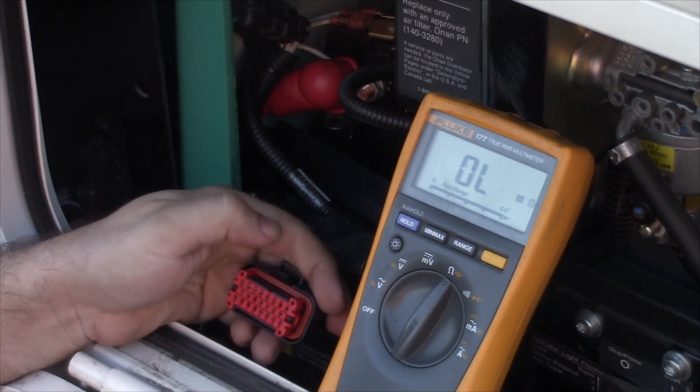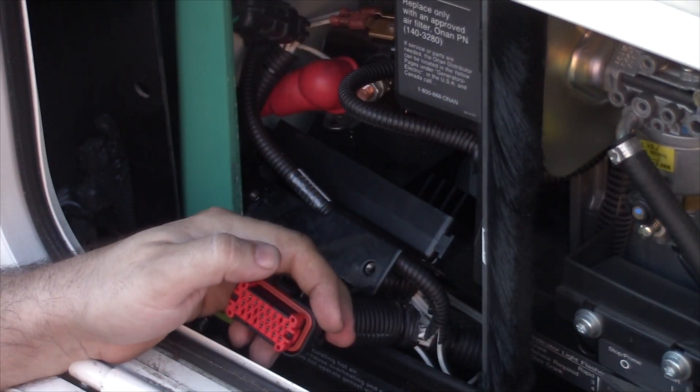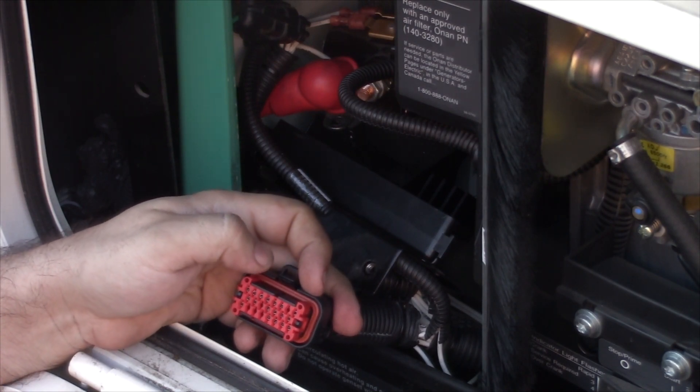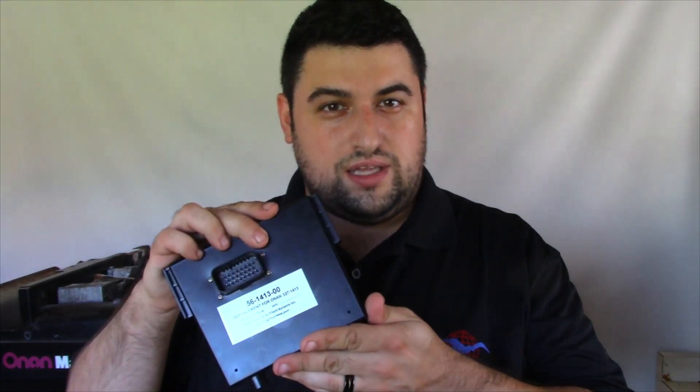That is measuring your windings on the QG4000. The Marquis Gold generators — the early model Marquis Gold generators — use exactly the same connector and it's pinned exactly the same way. That's how you measure the windings on a QG4000 and a Marquis Gold-style generator using that 23-pin connector. All of the results from these tests will tell you whether or not the generator is functional and working properly inside, and all your windings are okay. If everything comes out okay, chances are you just need a replacement control board. We proudly offer replacements here at Flight Systems for the 1413-style controls and the 5374-style control used in the Marquis Gold.